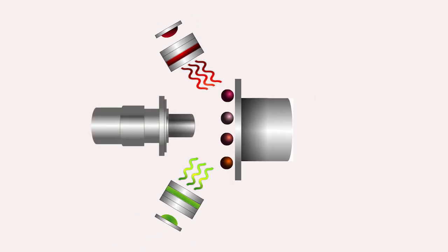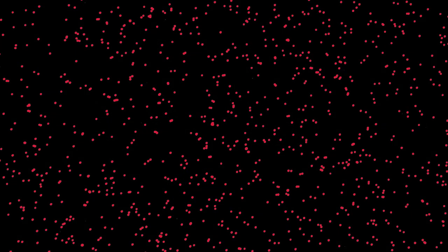In CCD imaging, beads are held in a monolayer with a magnet. One LED is used to excite the fluorescence of the beads for identification, and a second LED excites and quantifies the assay reporter molecules. The instrument records dozens of readings for each bead set and produces a distinct result for each analyte in the sample.